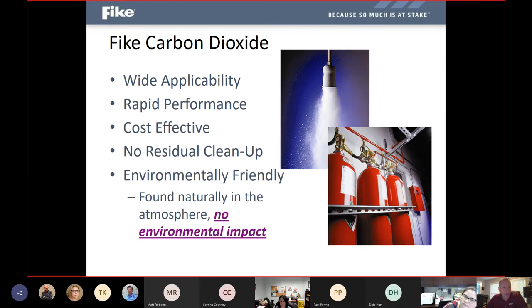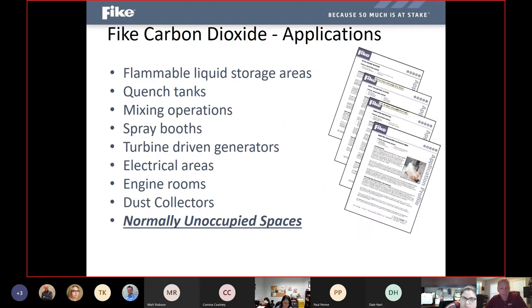And of course, carbon dioxide systems, CO2, still have a very wide range of applicability. They're very rapid to perform because they are complete oxygen displacement wherever those nozzles are aimed. They are still environmentally friendly because it's a naturally occurring element in the atmosphere, but again, they're very detrimental for human occupants that might be nearby if a system ever goes off. So where we mostly see carbon dioxide systems being used are in very heavily industrial applications where you're not likely to have somebody in that specific area or inside that room when a fire is expected to occur and the system to go off. So we only really recommend or use them in normally unoccupied spaces.